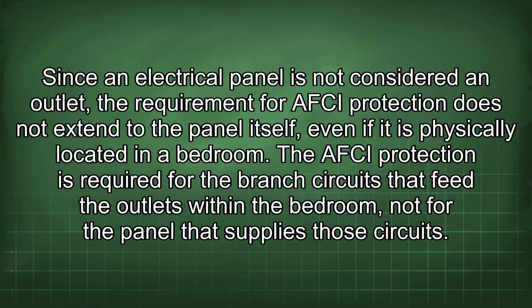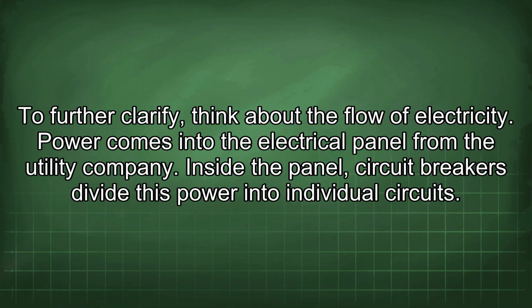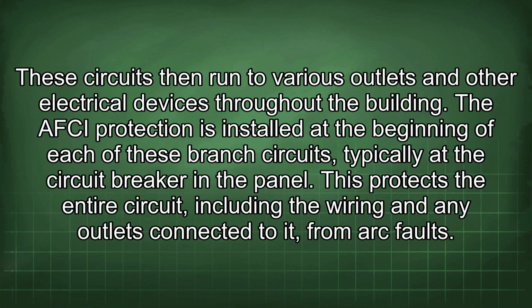The AFCI protection is required for the branch circuits that feed the outlets within the bedroom, not for the panel that supplies those circuits. To further clarify, think about the flow of electricity. Power comes into the electrical panel from the utility company. Inside the panel, circuit breakers divide this power into individual circuits. These circuits then run to various outlets and other electrical devices throughout the building. The AFCI protection is installed at the beginning of each of these branch circuits, typically at the circuit breaker in the panel. This protects the entire circuit, including the wiring and any outlets connected to it, from arc faults.